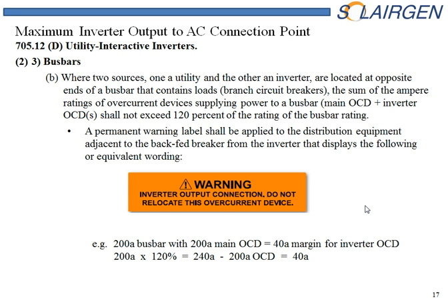This is a label that goes right next to the back-fed breaker into the panel. This is the inverter breaker. We place this at the opposite end of the main breaker to keep from overloading the bus bar. So this is a label that has to be on. People overlook this, ignore it, and don't install it. If I was an inspector, I'd go straight for the panel and look for it. So it needs to be there next to that breaker, identifying it as the breaker that cannot be moved from that location.